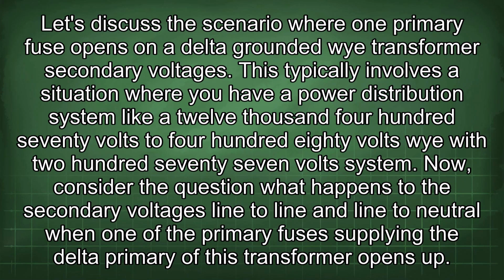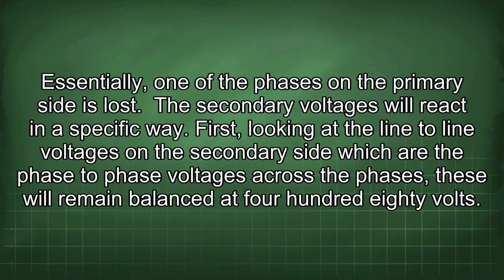Let's discuss the scenario where one primary fuse opens on a delta-grounded Y transformer and look at the secondary voltages. This typically involves a power distribution system like a 12,470 volts to 480 volts Y with 277 volt system. Now consider the question: what happens to the secondary voltages, line to line and line to neutral, when one of the primary fuses supplying the delta primary of this transformer opens up? Essentially, one of the phases on the primary side is lost. The secondary voltages will react in a specific way.